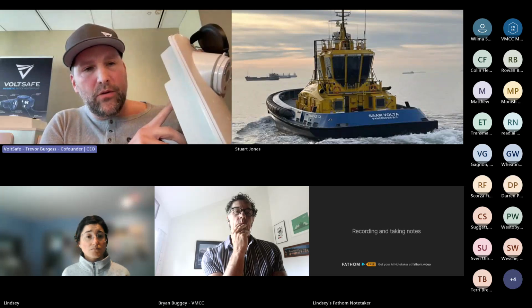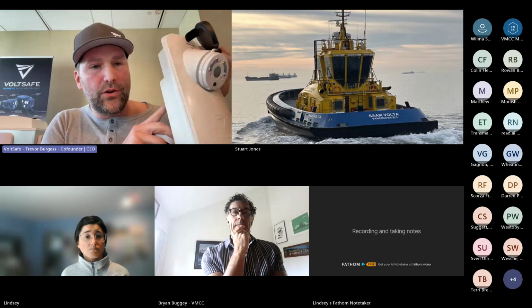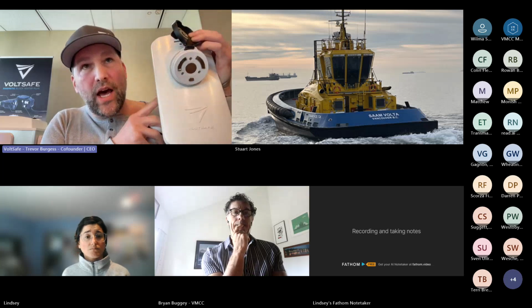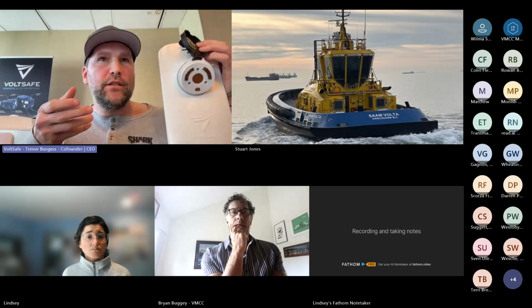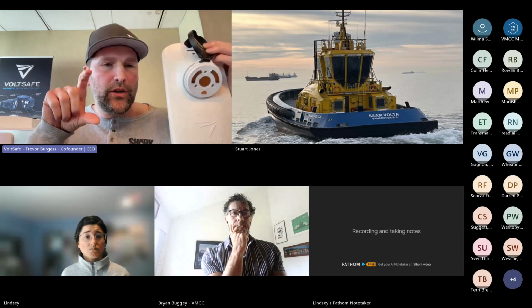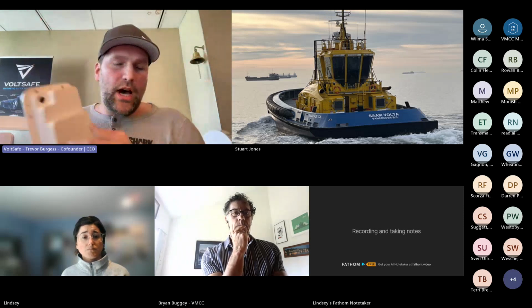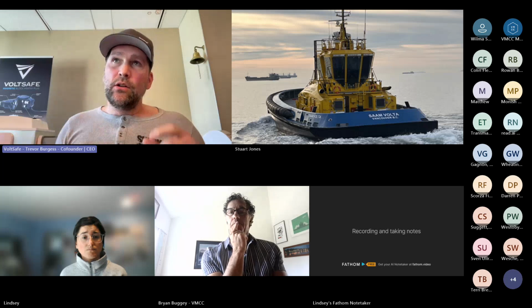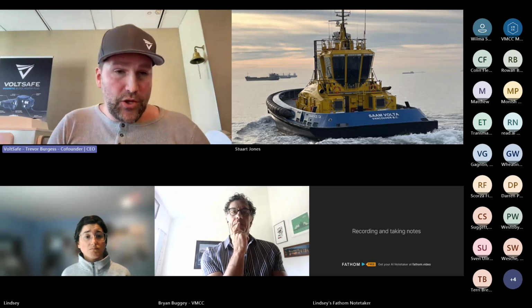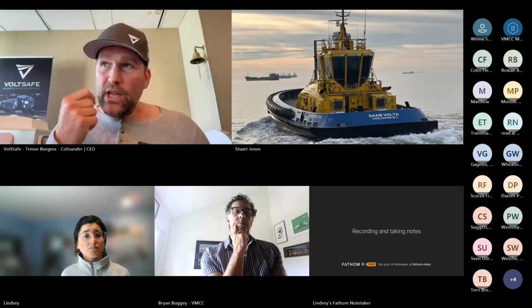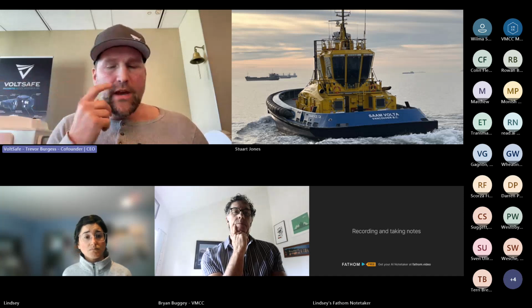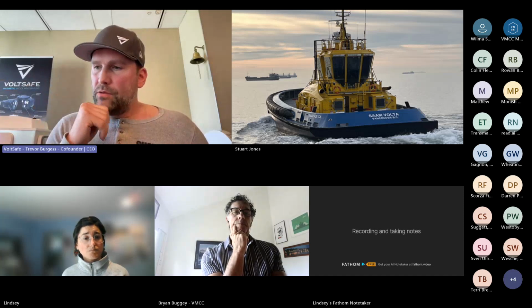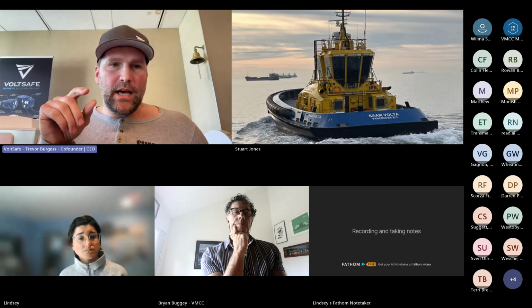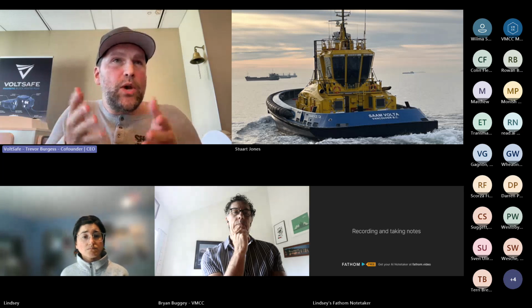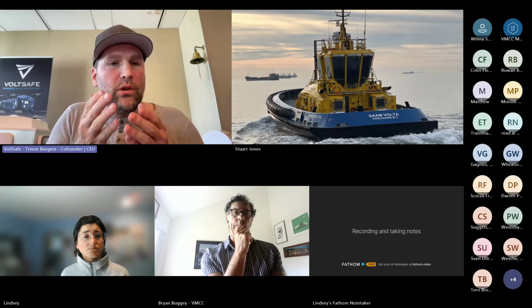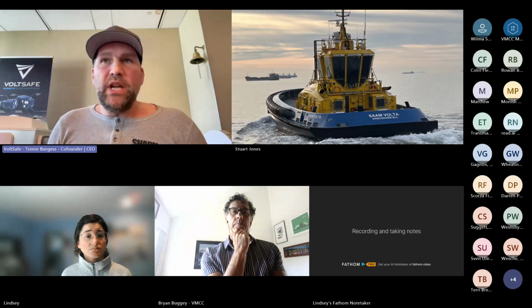Inside the box, it will be ground fault protected and certified, so you won't have to buy a $400 breaker for your marina. Right now marinas in Canada have these $400 breakers. The US has to have those at every slip - for a 30 amp they have to have it, for a 50 amp they have to have it. A 30 amp breaker is about $300 or $400 US, and it trips if the boat has more than 30 milliamps of leakage.